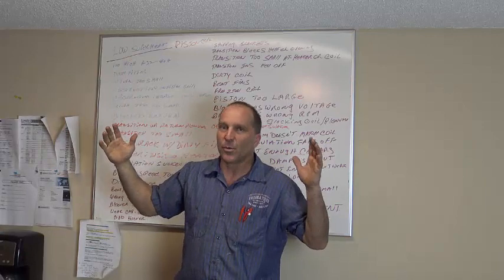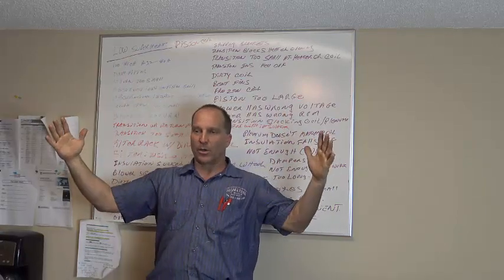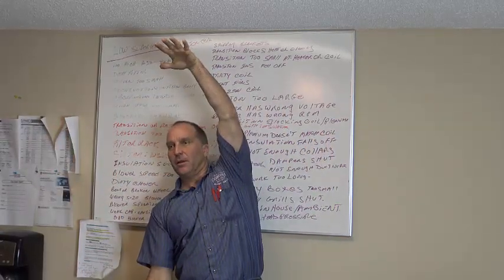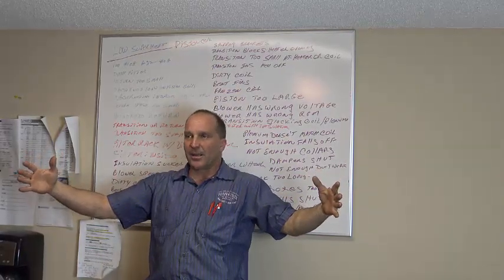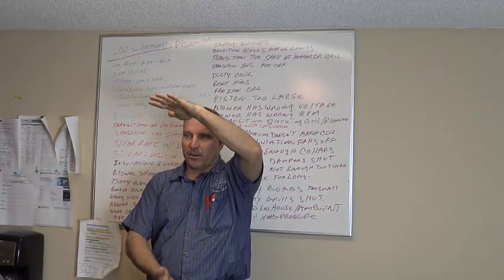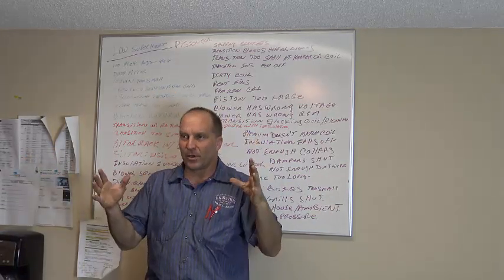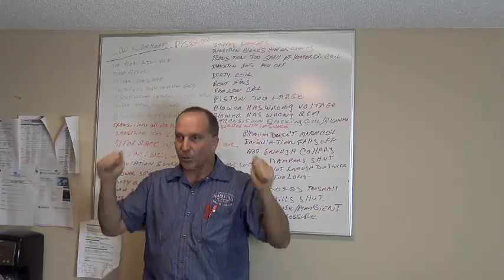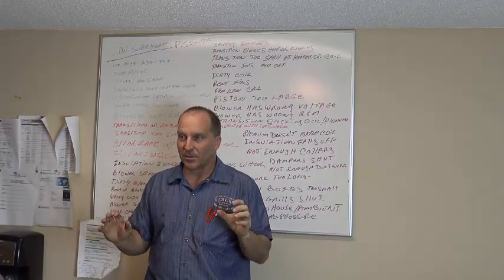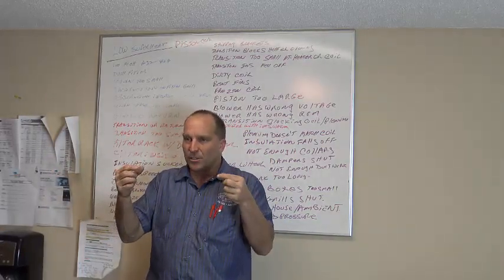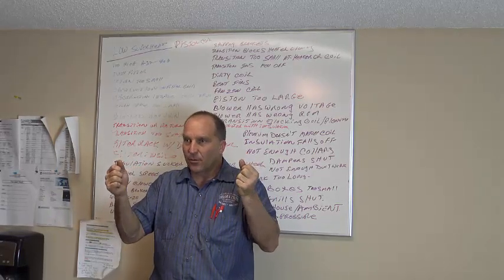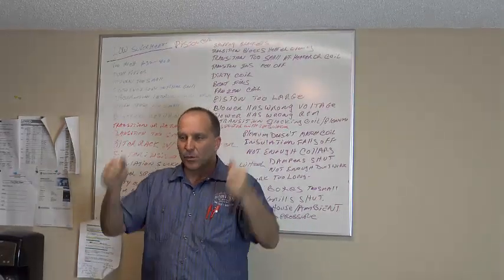So look at it this way. If you've got a filter grill that's this big, then it can allow a lot of airflow through. So let's just take your original 20 by 20 return filter grill that you were putting a filter in that you could read a newspaper through, one of the little fiberglass ones, and it was working fine. Then you go buy one of those 1-inch thick filters that you can't see through, you can't hardly blow through, and you stick that in there.